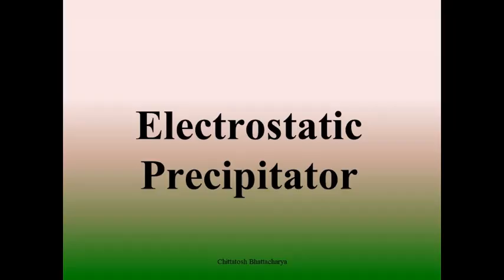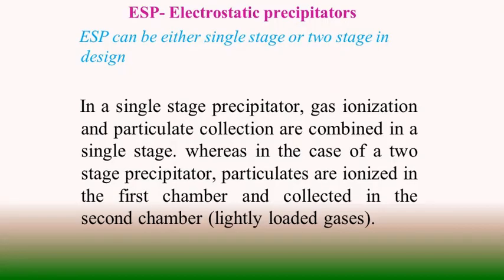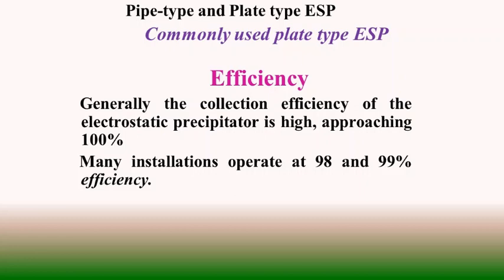The next type of dust separation and collection system is the electrostatic precipitator. An ESP can be either single stage or two stage. In a single stage precipitator, gas ionization and particulate collection are combined in one stage. In a two-stage system, particulate ionization occurs in the first chamber and collection in the second. There are two types of ESPs: pipe type and plate type, but plate type ESPs are mostly found in industries. The efficiency of an ESP is very high — most installations operate between 99 to 99.9% efficiency.